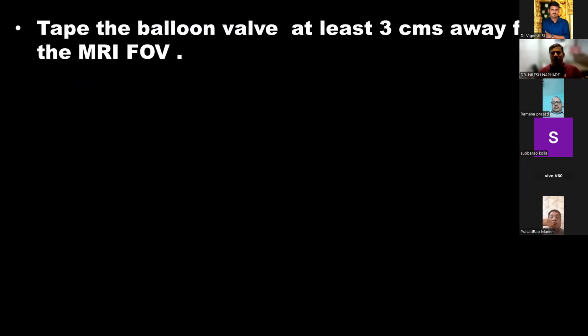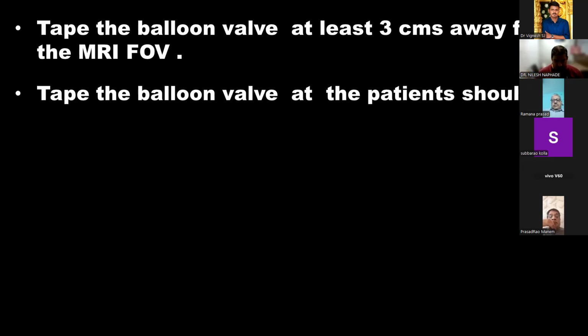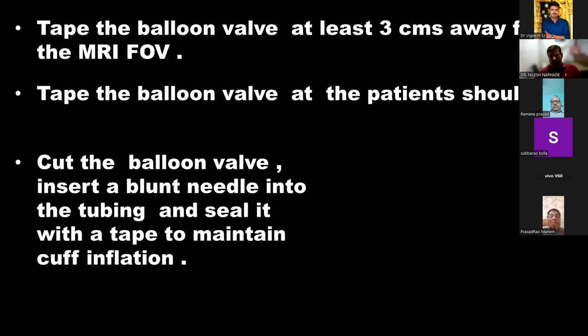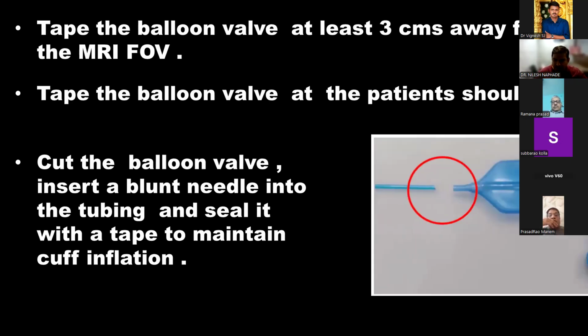Tape the balloon valve at least 3 centimeters away from the MRI FOV. FOV stands for field of view. So whatever is undergoing the MRI scan, keep it 3 centimeters away from that. If the patient's chest is being examined, keep the balloon 3 centimeters away from the chest. Tape the balloon to the patient's shoulder. Or if that is not possible because the head, face or neck area is being scanned, cut the balloon valve like this.